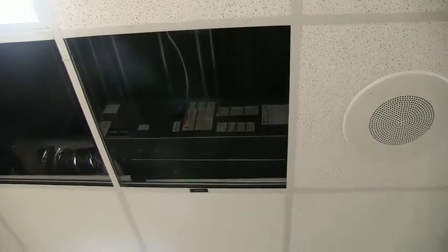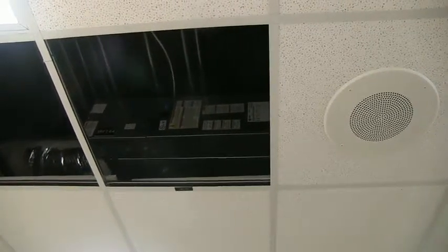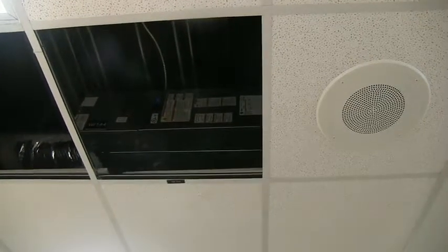All right, if we look above the ceiling here, this is a Trane VAV. It's got 2 cabinets. The cabinet to the left is the control cabinet and the damper actuator cabinet. The cabinet to the right is the high voltage cabinet that contains the heater contactors, fuses, and disconnects for the VAV. Operation is basically, as it gets closer to set point, it'll close the actuator down to reduce the airflow for the space. In the heating mode, it'll go 100% open.